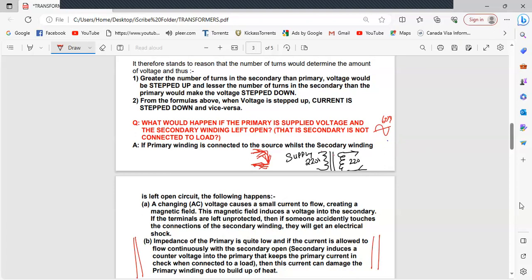I made this mistake once, not with a transformer but with a solenoid coil. Your solenoid coil has a coil outside and a core inside, which either opens or closes a valve. That core is acting as the secondary. If you take out the core of the solenoid, nothing comes into your primary, so it's not going to be doing that, and your coil is going to get burnt out. This happened long ago, when in the olden days we never used to have PLCs for purifiers.